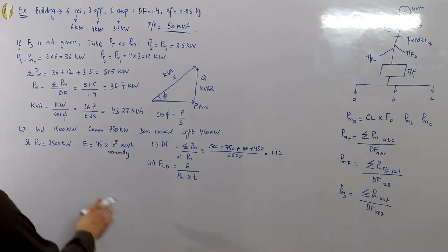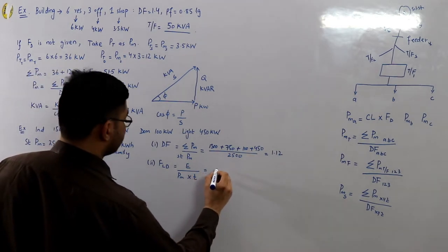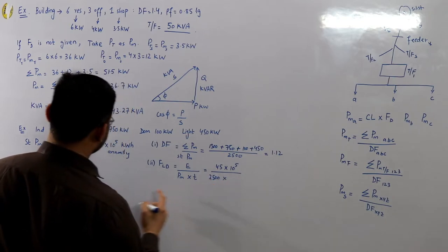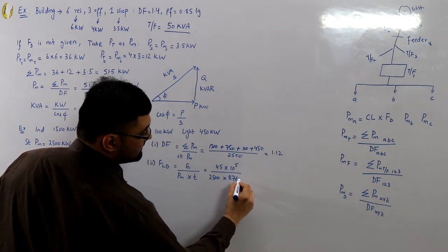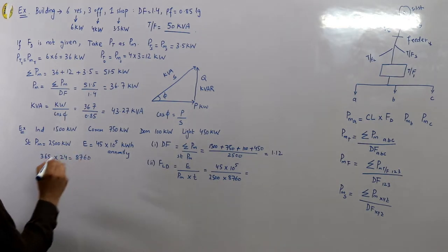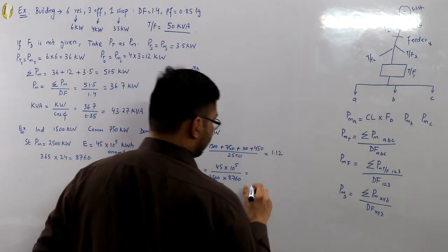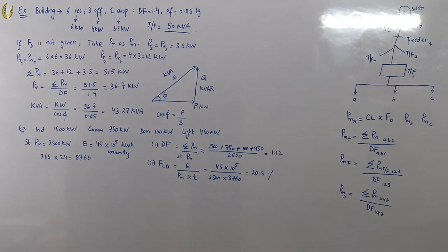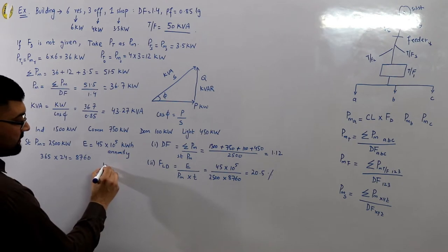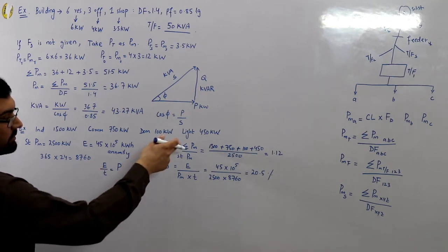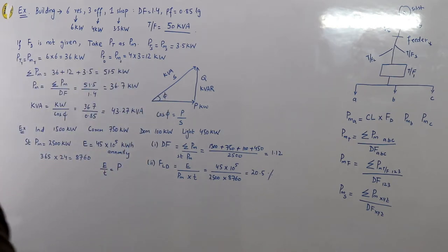For the load factor: energy ÷ (maximum demand × time). Energy is 45 × 10⁵ kWh, maximum demand is 2500 kW, and time is 8760 hours per year (365 × 24). The load factor comes out to be 20.5% — a very low value. Note: E ÷ T gives average load, so you can also find load factor as average load ÷ maximum demand.